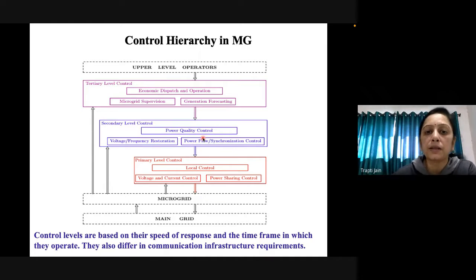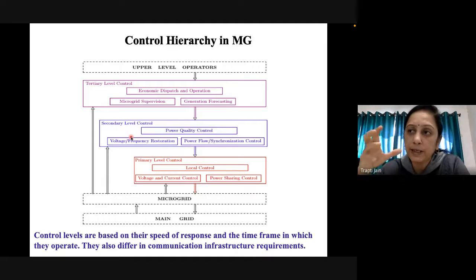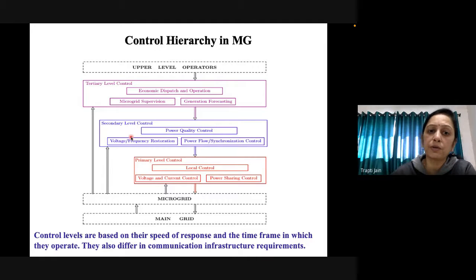This secondary level control is slower compared to the primary level control, operating on a time scale of 1 to 10 seconds. It maintains power quality by regulating the grid frequency, and is also responsible for voltage and frequency restoration and power flow synchronization control.